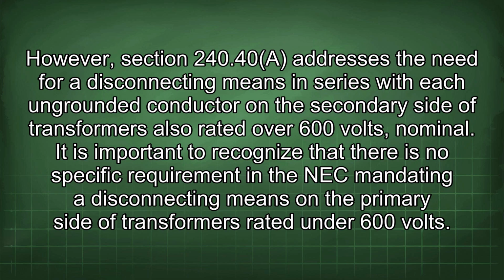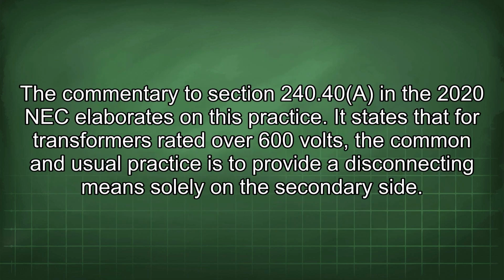It is important to recognize that there is no specific requirement in the NEC mandating a disconnecting means in the primary side of transformers rated under 600 volts. The commentary to Section 240.40 in the 2020 NEC elaborates on this practice. It states that for transformers rated over 600 volts, the common and usual practice is to provide a disconnecting means solely on the secondary side.